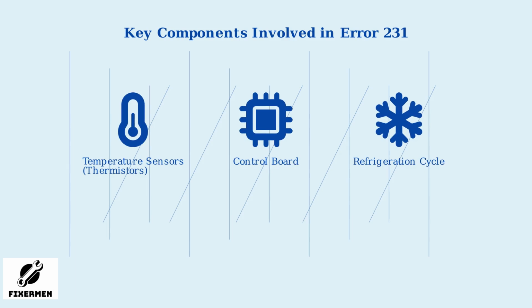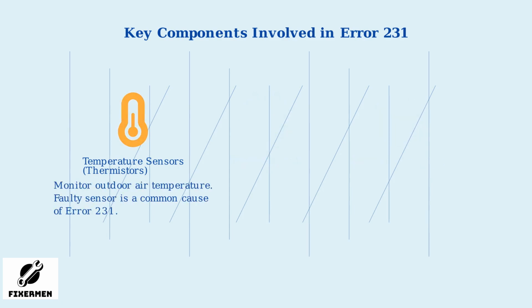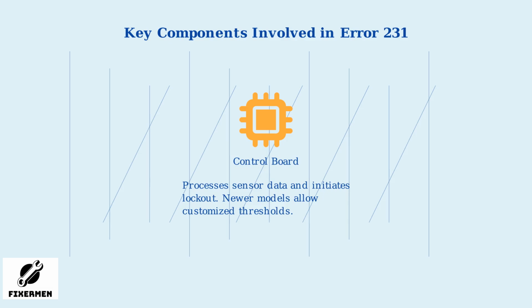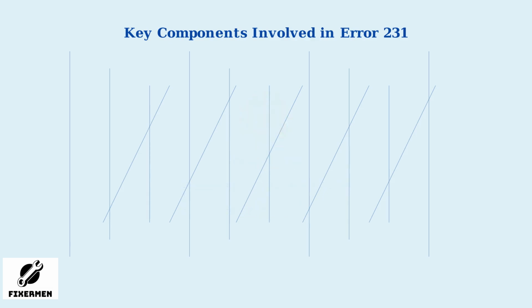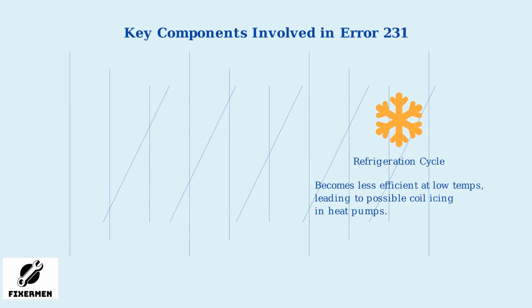Several components play a role in triggering Error Code 231. The most important are temperature sensors, the control board, and the refrigeration cycle. Temperature sensors, specifically thermistors, monitor the outdoor air temperature. A faulty sensor is a common cause of Error 231. The control board processes the sensor data and initiates the lockout. Newer models allow for customized temperature thresholds. The refrigeration cycle in heat pumps becomes less efficient at low temperatures, leading to possible coil icing.